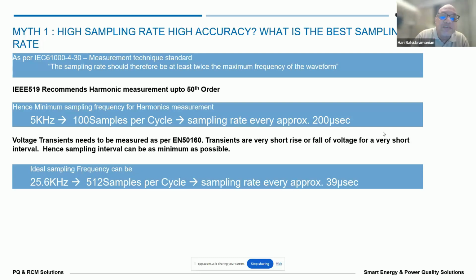So this is a very simple sampling frequency, and the samples per cycle is basically the sampling frequency divided by the frequency. For example, if I have a 5 kilohertz sampling frequency, then in a 50 hertz system, 100 samples per cycle is what would come. So the sampling interval would be every 200 microseconds. So that's how it is calculated.